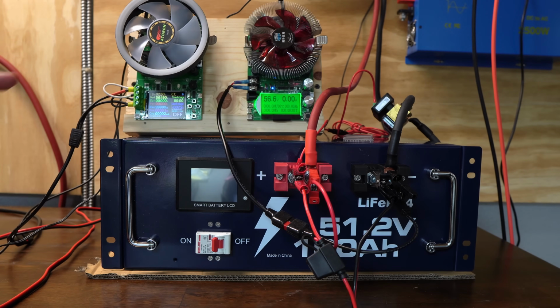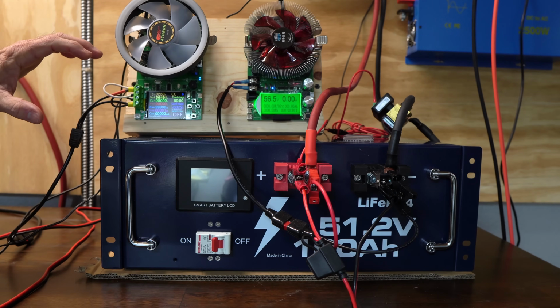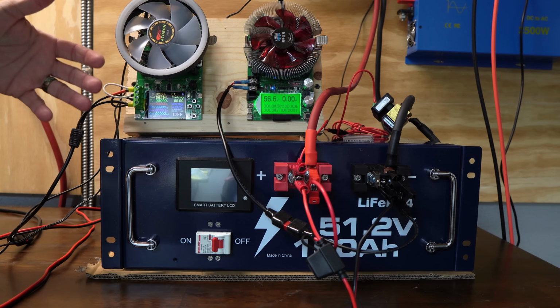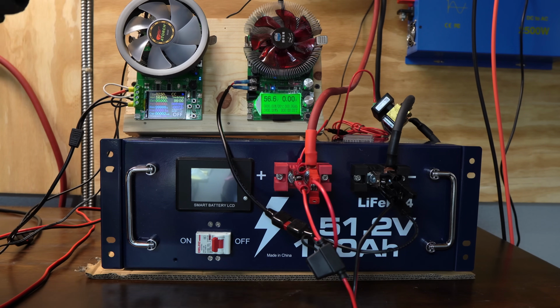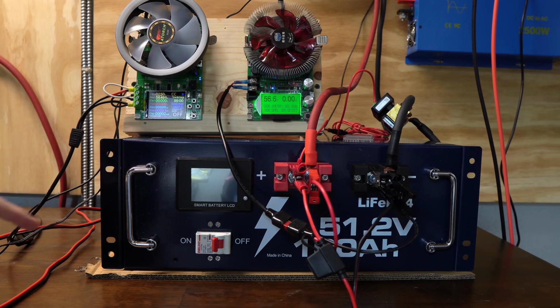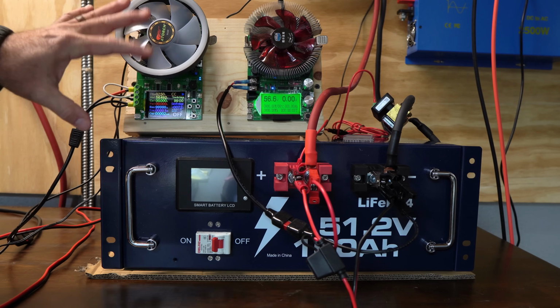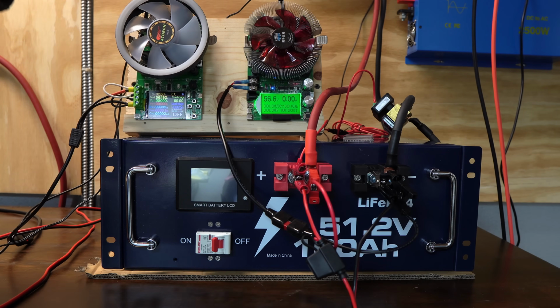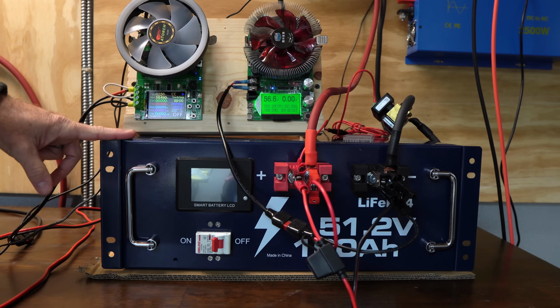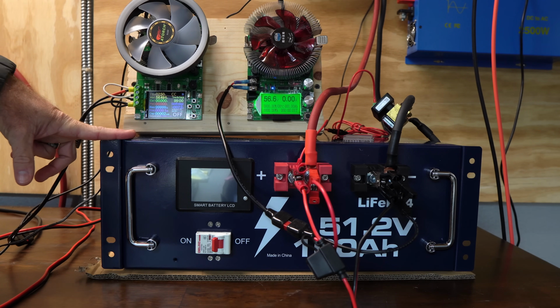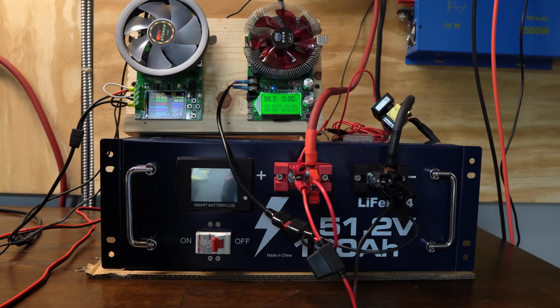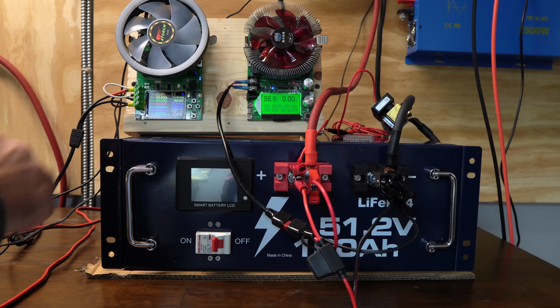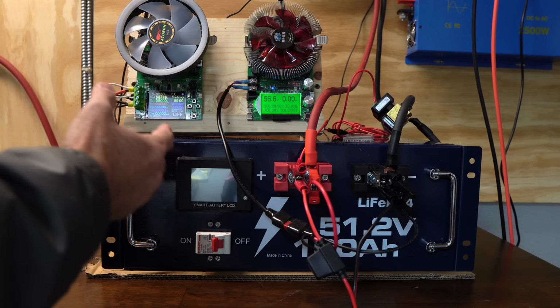All right, I've rigged up a couple of DC battery testers here. Now, these are not particularly high power ones. They max out at somewhere around 130 to 140 watts. So I've got two of them connected here with alligator clips to this battery, and we're going to record the total. We're going to have to add these together, the total watt hours we can get usable out of this 100 amp hour battery. And since it's a 51 volt battery or 48 volt battery nominal, we have to limit the current to a very low number.